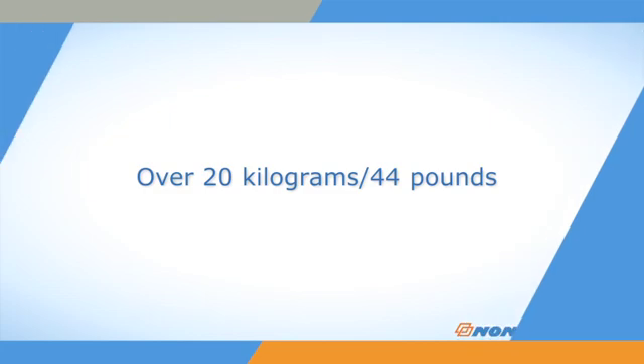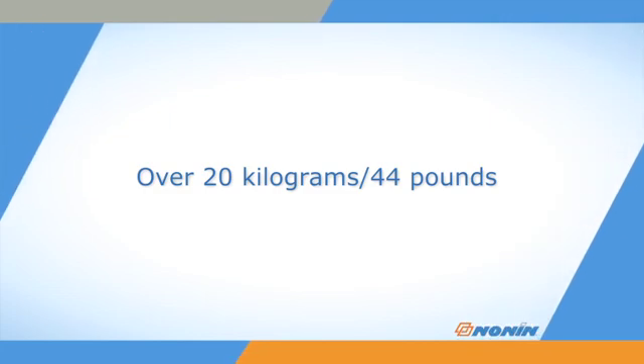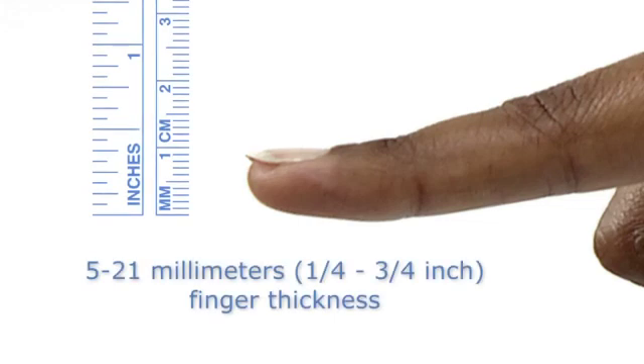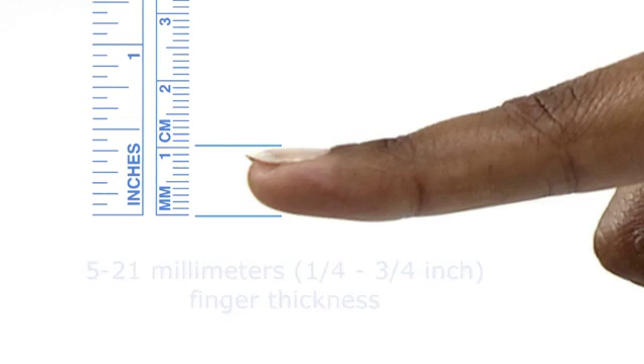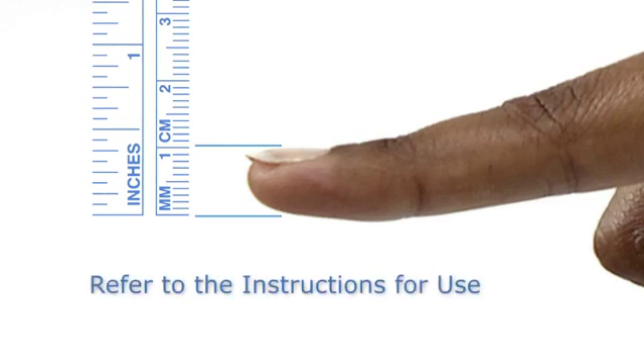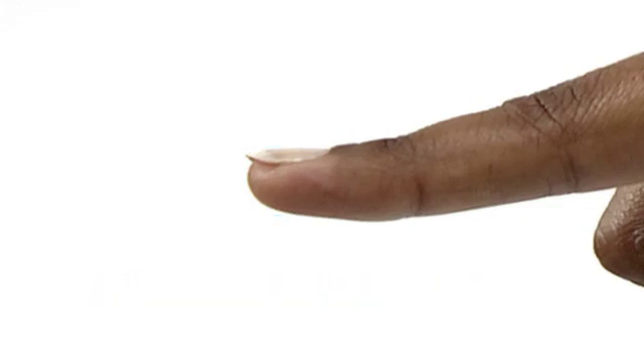The 8000J and 8000JWO WristOx2 sensors are designed for patients over 20 kilograms or 44 pounds in weight. They will fit fingers between 5 and 21 millimeters or one quarter to three quarters inch in thickness measured at the center of the fingernail. Ensure the flex sensor size is appropriate for the patient. Refer to the instructions for use.